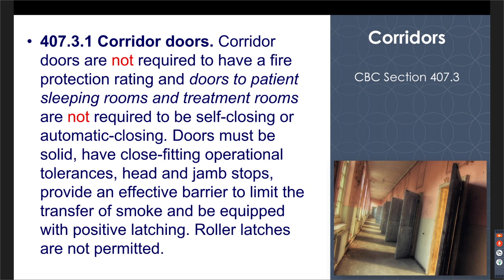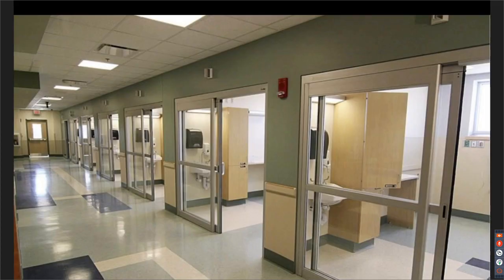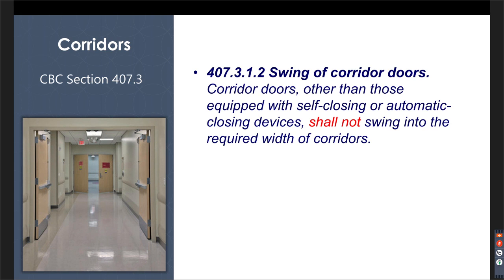That door might be on the corridor, that would have to be rated, of course. But if it's doors to a patient room or treatment rooms or certain offices, they may not need to be rated. They don't need to be self-closing, but they need to resist the passage of smoke. Some examples there. So we mentioned that the doors don't have to be self-closing. That is as long as they don't swing into the required width of corridors. If the doors swing into the required width of the corridor, those do have to have self-closers or auto-closing devices.